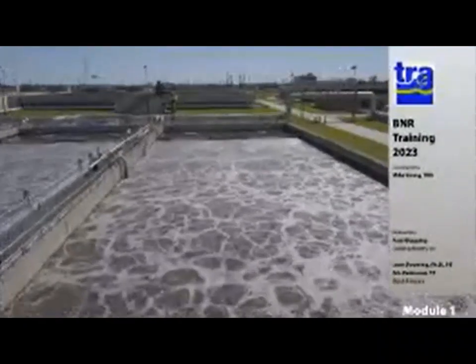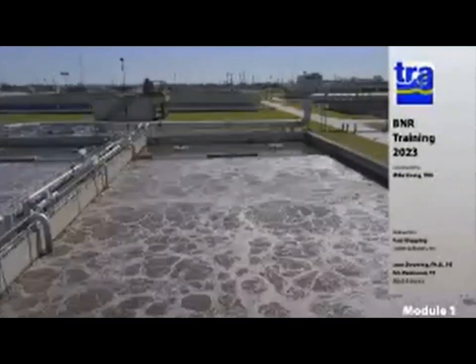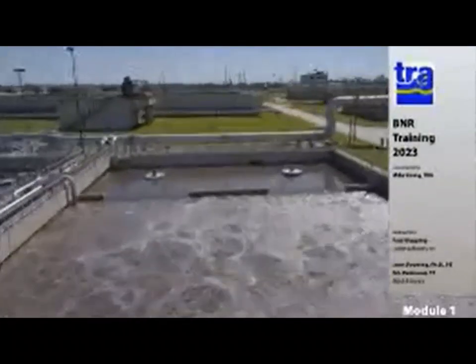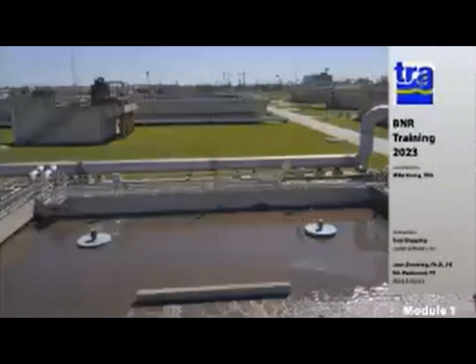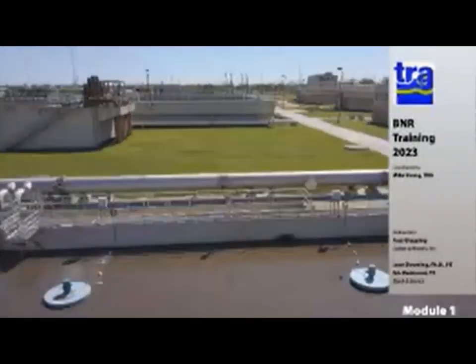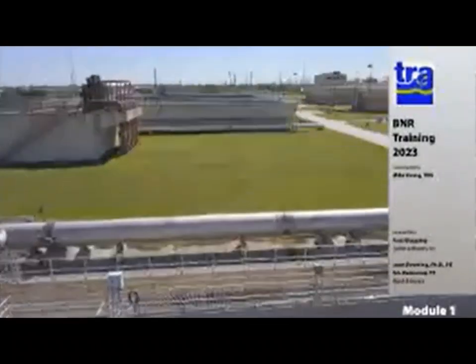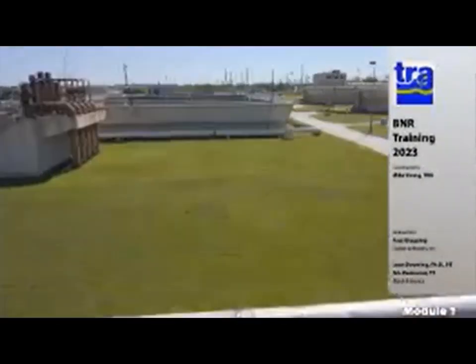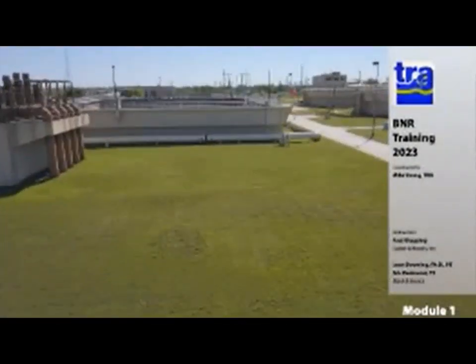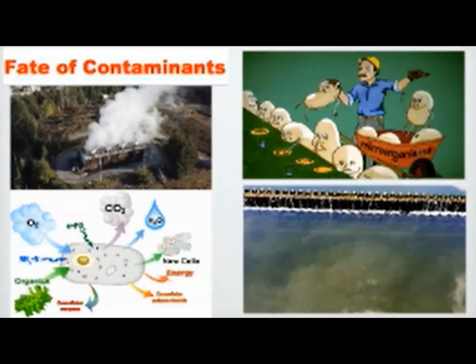activated sludge system that was then manipulated through the DO and the SRT. DO, dissolved oxygen; SRT, sludge or solids retention time. In other words, the sludge age, the average length of time a biological cell resides in the system. That concept of sludge age is something we will be leveraging as we go in terms of manipulating microbiology. All right.